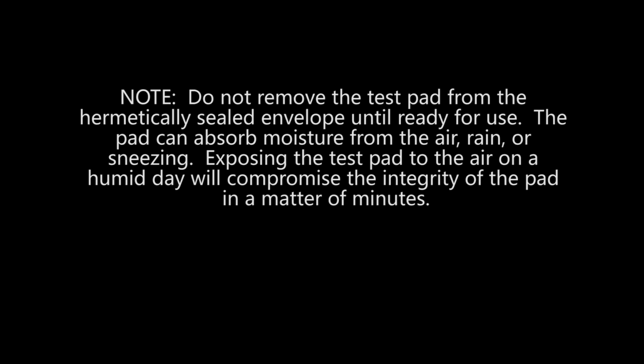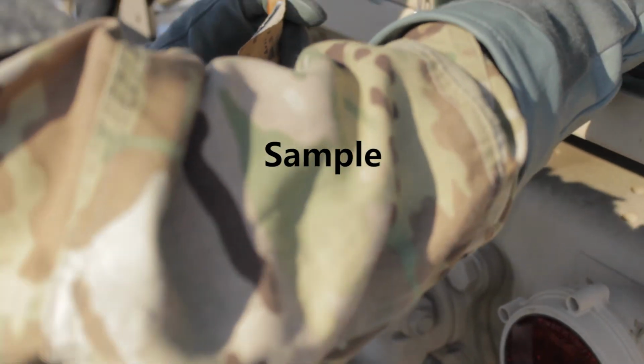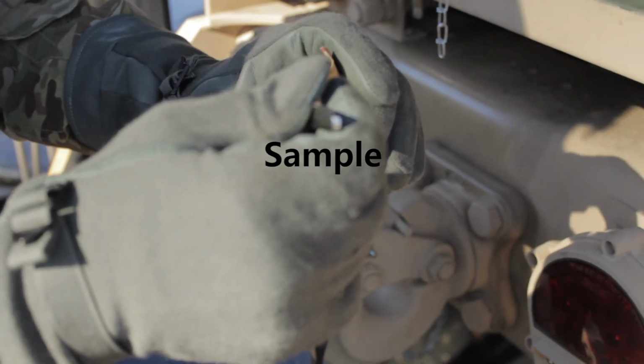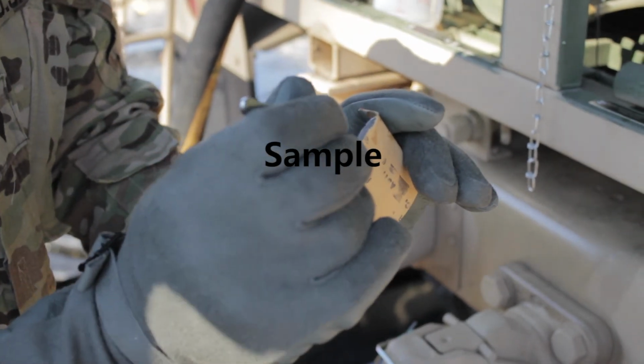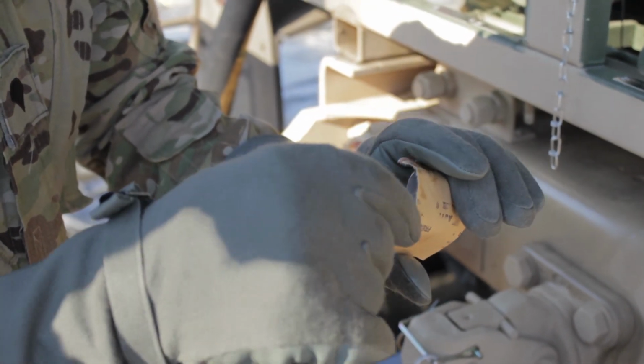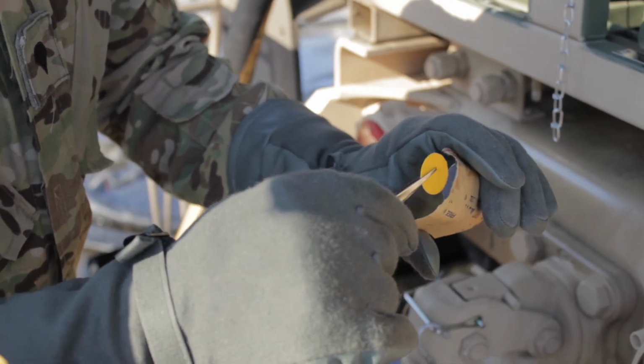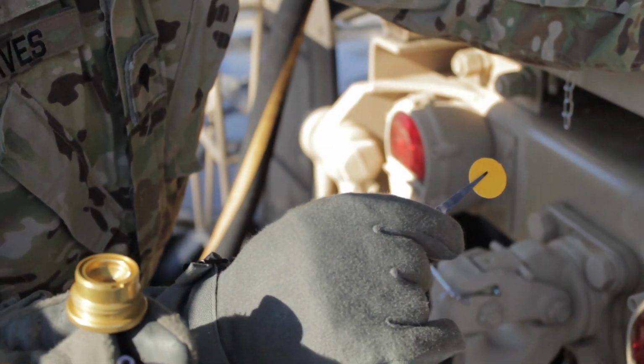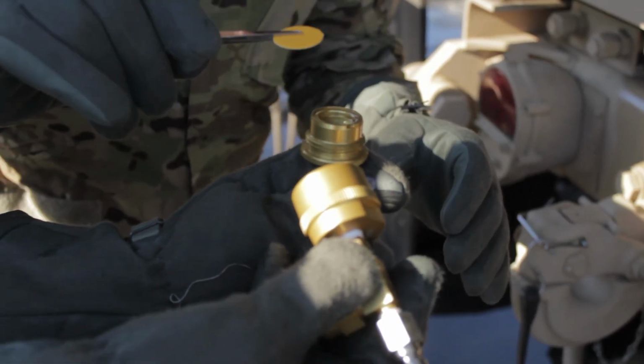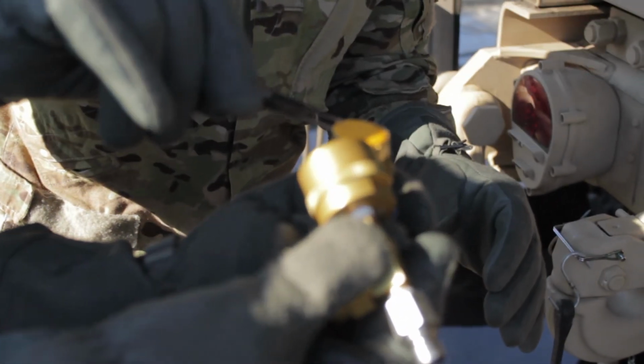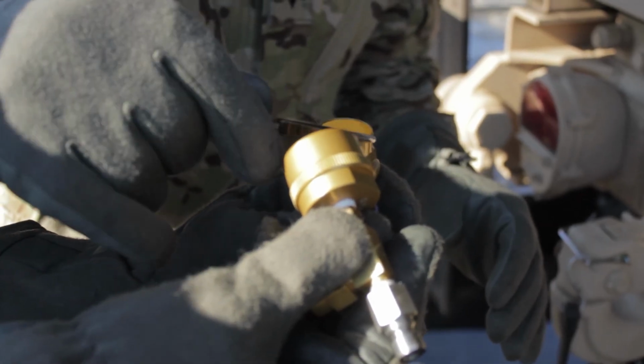Do not remove the test pad from the hermetically sealed envelope until ready for use. The pad can absorb moisture from the air, rain, or sneezing. Exposing the test pad to the air on a humid day will compromise the integrity of the pad in a matter of minutes. Using tweezers, remove the Aqua Glo test pad from the envelope. Observe the sample pad. If the sample pad has any discoloration, unevenness in dye content, or a faded yellow appearance, select another Aqua Glo test pad. Put the Aqua Glo pad into the sample test probe with the orange side, sunny side up, facing the inlet portion of the sample test probe.